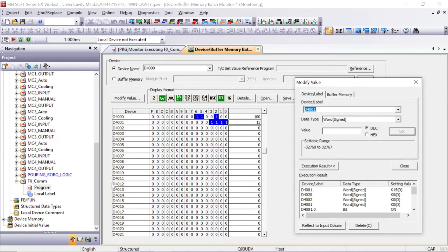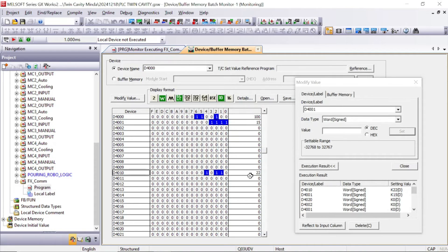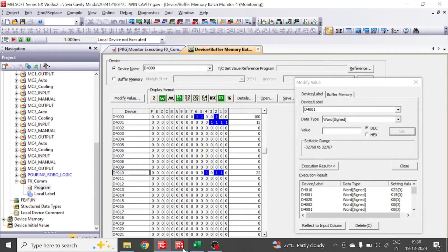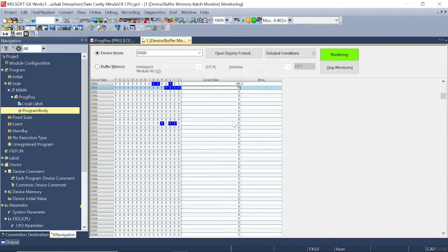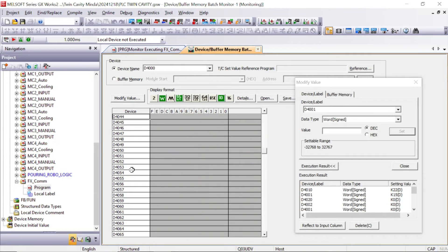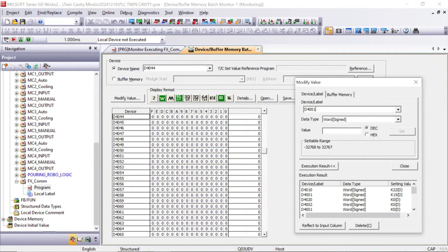Let's check another one. In D4010, let's put K22. D4010 now has value 22. Let's check in the FX5U PLC — it shows 22. In this way, 100 registers of data will move from D4000.